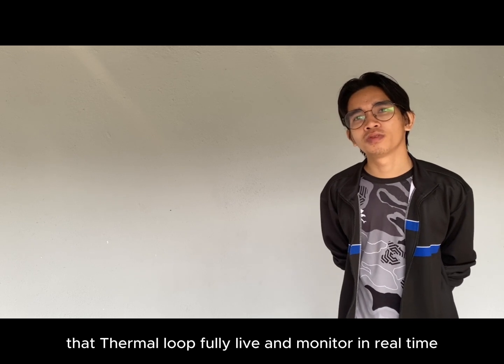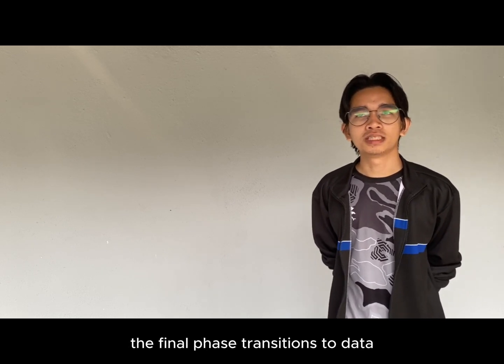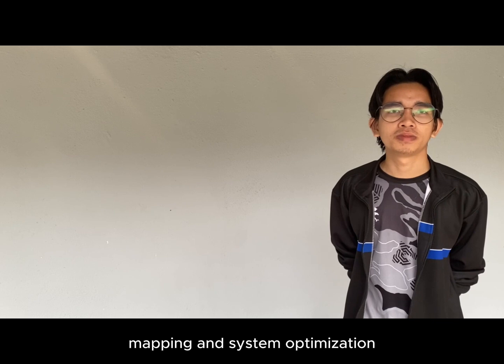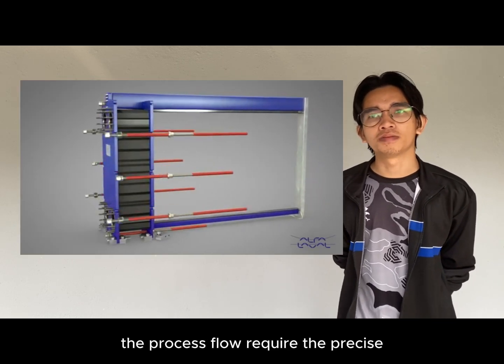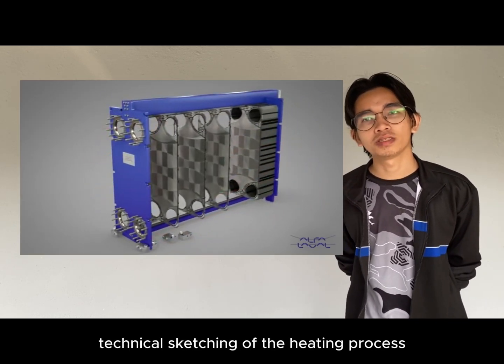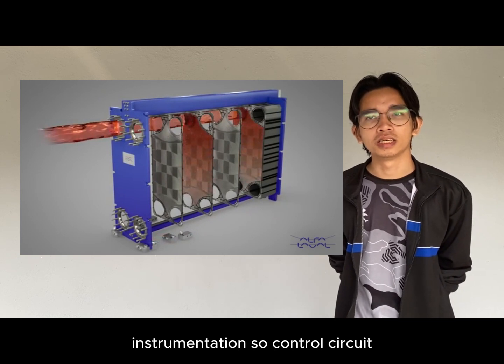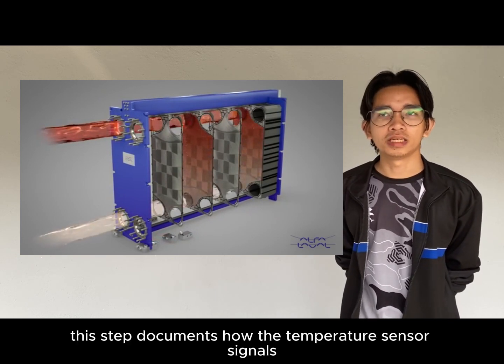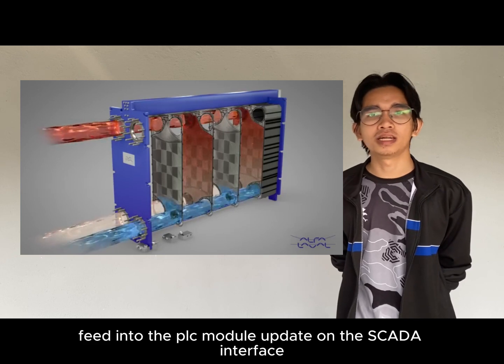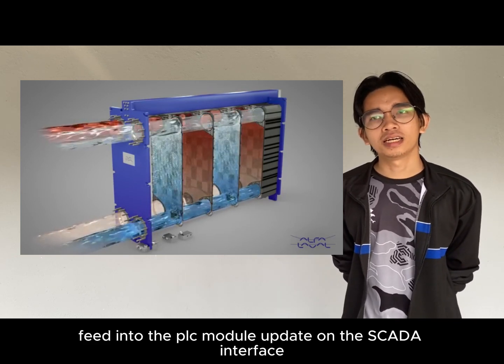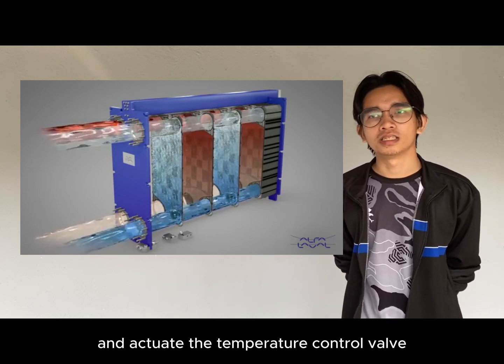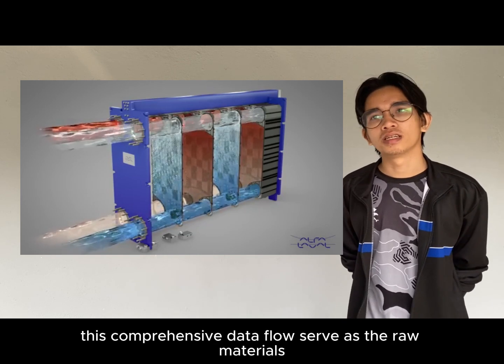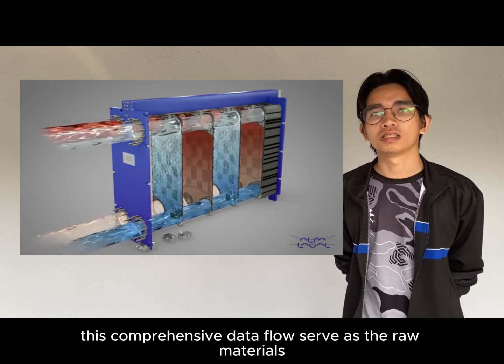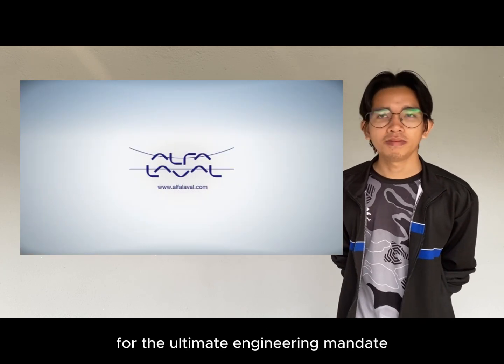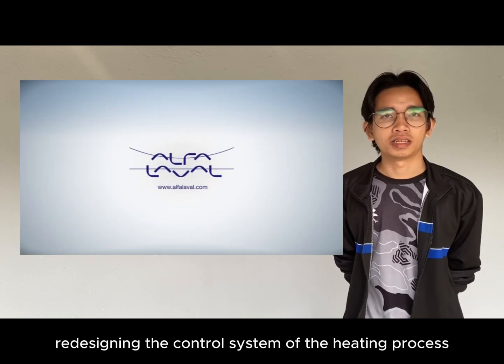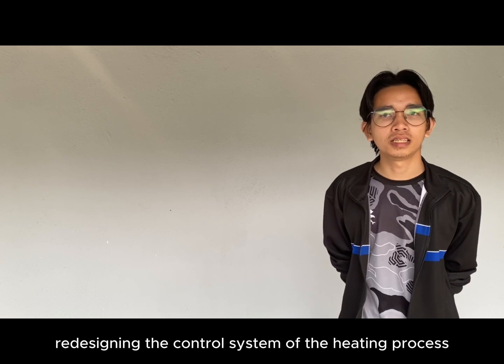With that thermal loop fully live and monitored in real time, the final phase transitions to data mapping and system optimization. The process flow requires the precise technical sketching of the heating process, instrumentation, and control circuit. This step documents how the temperature sensor signals feed into the PLC module, update on the SCADA interface and actuate the temperature control valve. This comprehensive data flow serves as the raw material for the ultimate engineering mandate, redesigning the control system of the heating process.